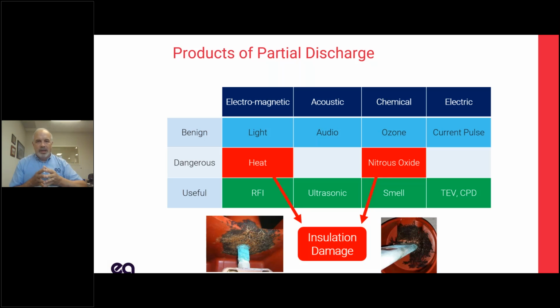In the acoustic range, which is sound waves, this is not an electromagnetic effect. This is acoustic. It's sound, travels through liquids, solids, through gas, through air. It creates a little bit of energy in the audio band, which is what we can hear, and a lot in the ultrasonic band. So that is sound waves, but they're above the range of human hearing, up in the 40 kilohertz range. And that is a great method for detecting.